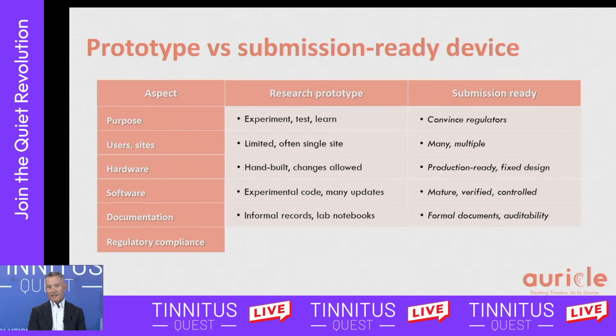And finally, for regulatory compliance, research prototypes often feature little or no requirements because they are typically not intended for a medical device submission. But a submission-ready device must comply with all of the relevant international standards that apply. Just 3 examples of those would be ISO 14971 for risk analysis and assessment, IEC 60601 for safety and what's called essential device performance, as well as IEC 62304, which covers software development guidelines in medical devices. So as we understood the requirements for a submission-ready device better, that then led to our focus on creating a device that would be submission-ready or submission-compliant.